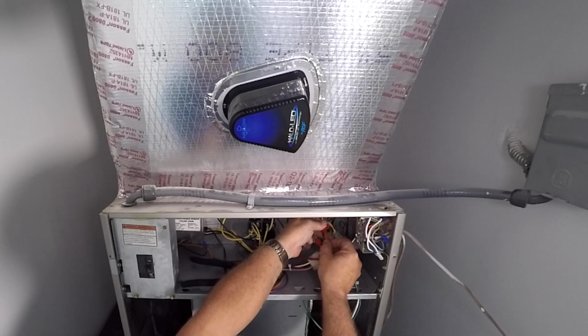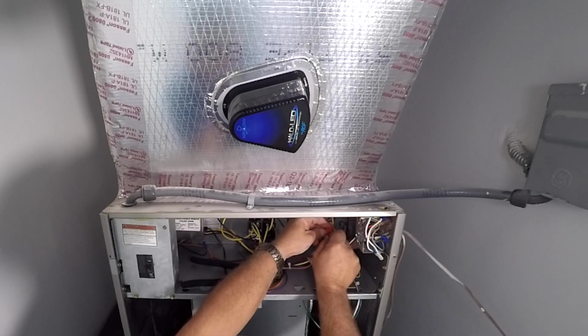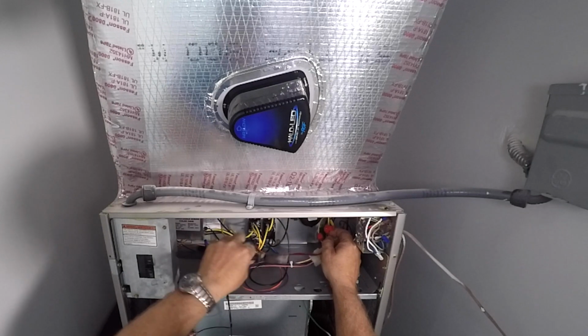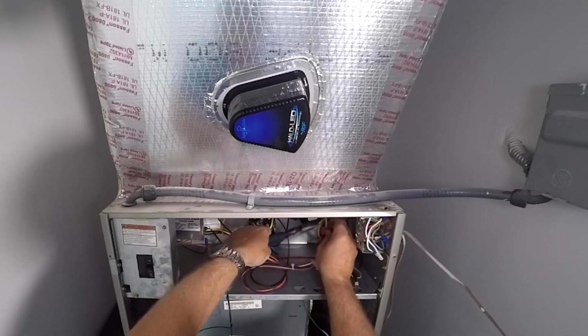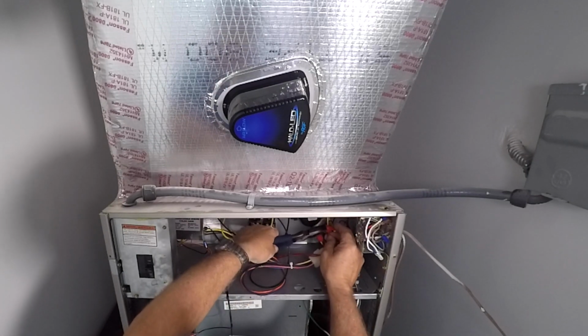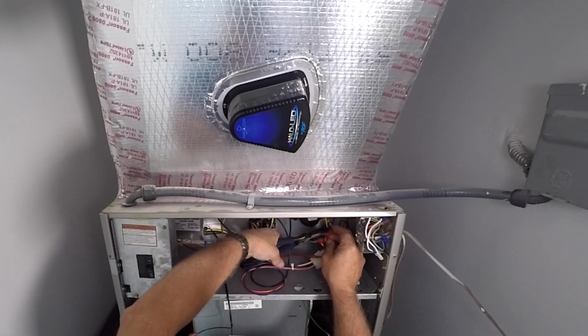In this situation, using the air switch, we leave the power on to the low voltage transformer all of the time, and we break the low voltage coming out of the transformer with the air switch.